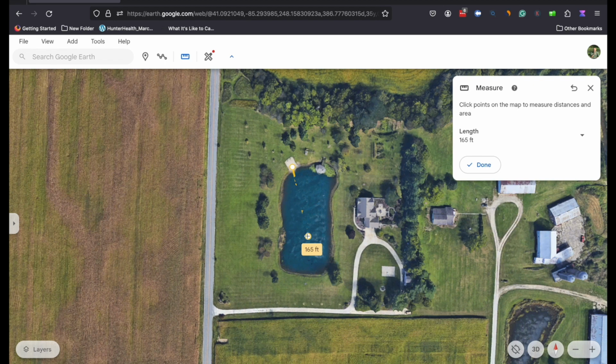For others, as I get closer to 300 feet and beyond, I might start to look at 5/8 inch line. This is inside diameter weighted airline, by the way, and certainly as you increase the depth, as you start to push 15, 20, 25 feet, I start to look at using the larger diameter airline almost no matter what my tubing run will be. This is all intended to keep back pressure down on the pump to a reasonable level. You don't want to put too much pressure on the pump, and it just helps it run more efficiently and stay cooler.